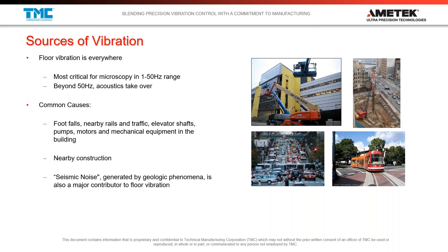We even consider seismic noise, but we're not talking about seismic noise like tremors and earthquakes. We're actually talking about an interesting geologic phenomenon, which we call the microseismic peak. And the microseismic peak is the cumulative effect of all the waves and all the world crashing on all the shores. And if you have a seismometer sensitive enough, you can really sense this low frequency peak from 0.2 hertz to about 0.4 hertz pretty much anywhere in the world. So floor vibration really comes from the ground, and it comes from all the inputs that are in the ground that I just mentioned.